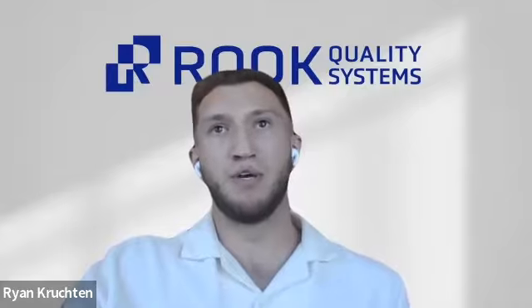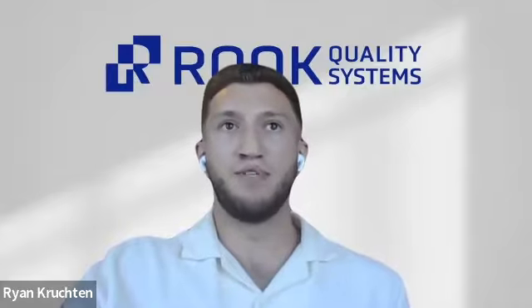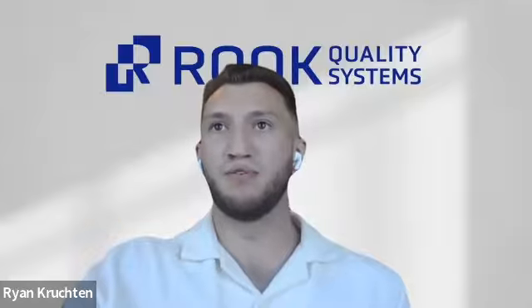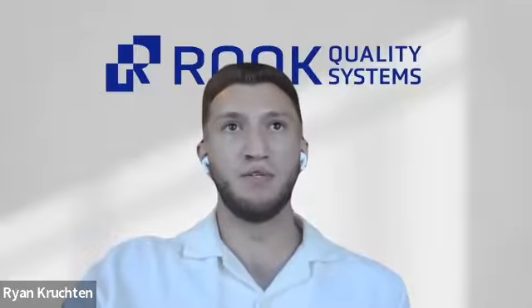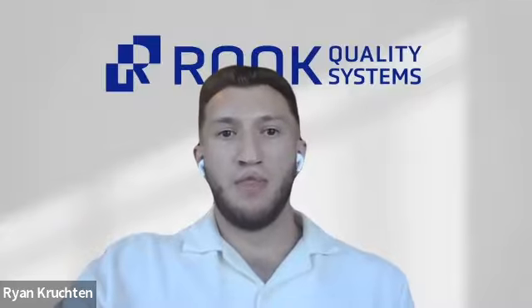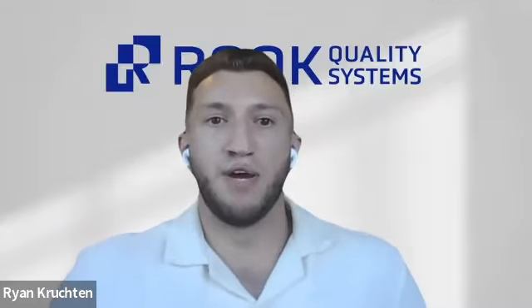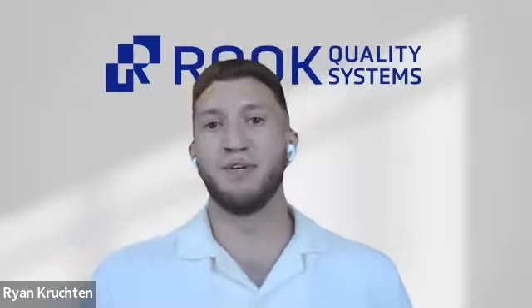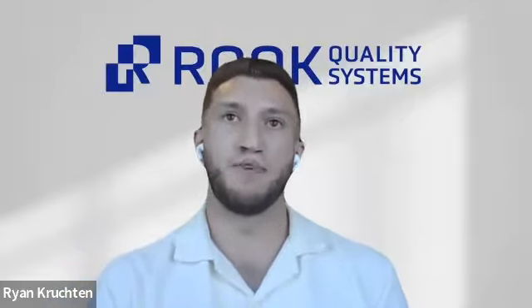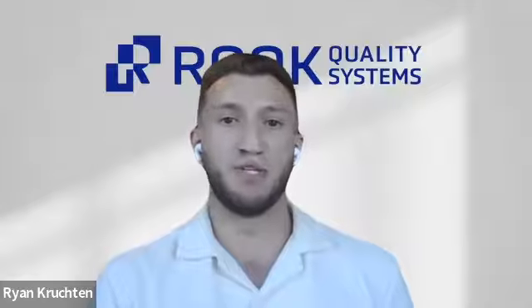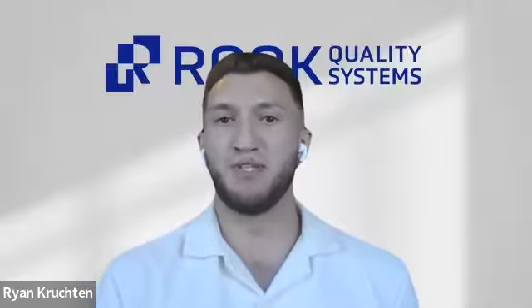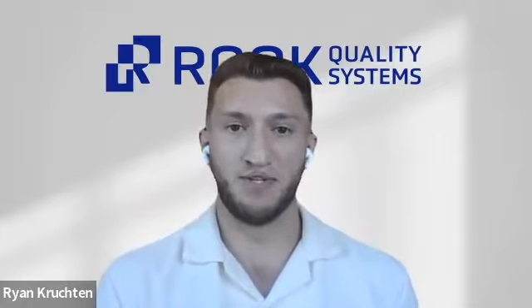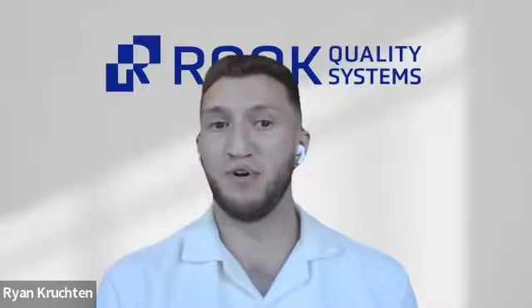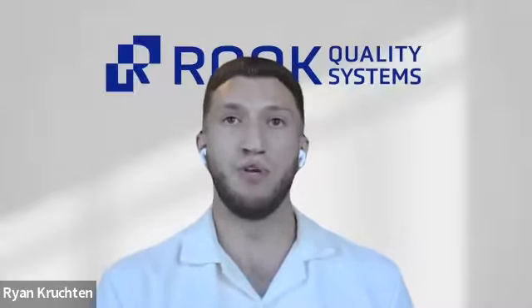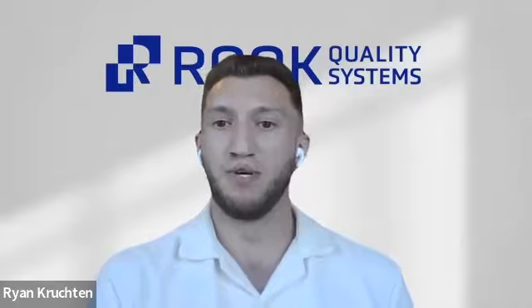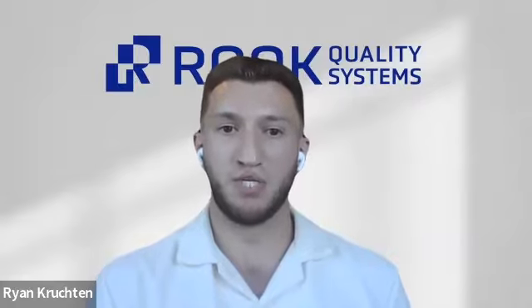So now let's switch gears a little bit and discuss how we ensure that we have FDA-compliant software documentation throughout the development process. So in 2023, FDA updated its guidance on content of pre-market submissions for device software functions. And the message was clear: documentation expectations depend on risk, just like everything else. So if your device performs low-risk software functions, like a minor calculator tool embedded in a broader system, you'll likely fall under the basic level documentation.